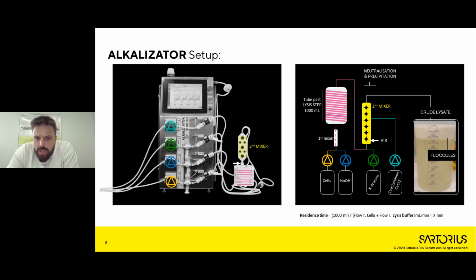The flow sensors are continuously measuring, and they work in a loop with the peristaltic pumps. So if the flow is a little bit up, the flow sensor will notice that and reduce the peristaltic pump a little bit, and so on. So it will continuously go for that target value, kind of an automatic mode as much as possible.